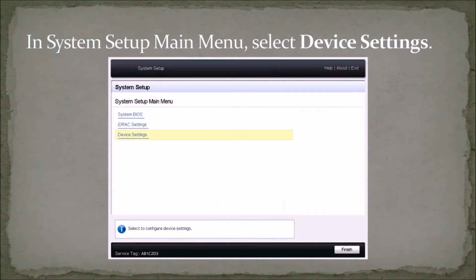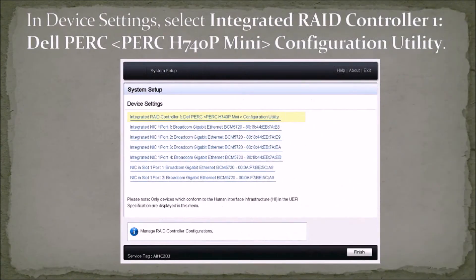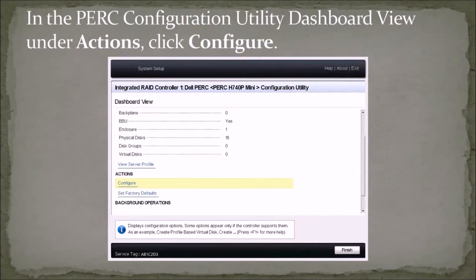In the system setup main menu, select Device Settings. In Device Settings, select Integrated RAID Controller 1, Dell PERC H740P Mini configuration utility. In the PERC configuration utility dashboard view, under Actions, click Configure.